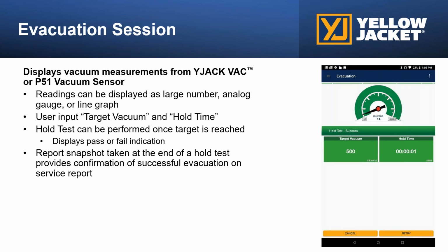So this is the evacuation, or pulling a vacuum. In this session, you can tell the digital manifold, or should I say the app, which will then speak to the digital manifold or to the micron gauge, the YJACK micron gauge that it's speaking to, what microns you want to have set as a target. And you would simply, on the slide on the right where it says 500 target vacuum, tap that with your finger and you could program it down to 1 micron. You can make it up to 1,000 microns. Also, that same information is above, and that information above can be represented by a number, an analog gauge, kind of how it is now, or in a bar graph.